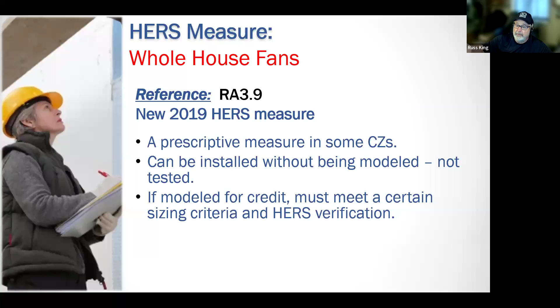Some of them are easier to test than others. So you definitely want to coordinate with whoever the installer is to make sure that whatever they're installing is the kind of fan that can be easily tested, and that it is installed in such a way that it can be easily tested. So installed unit airflow will be tested. Make sure it's installed somewhere that can be tested. Flat ceiling with no obstructions.